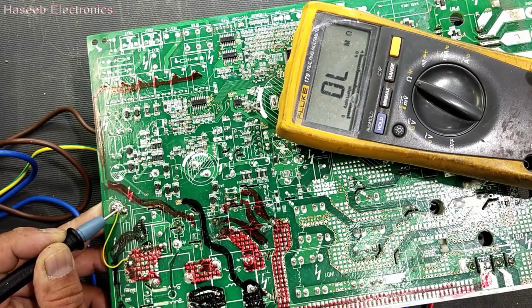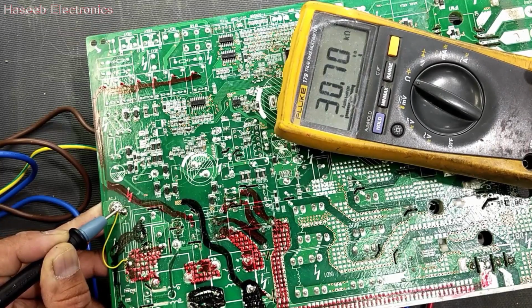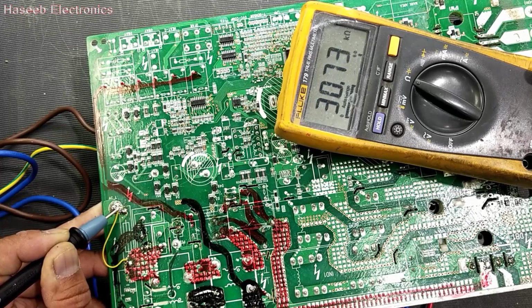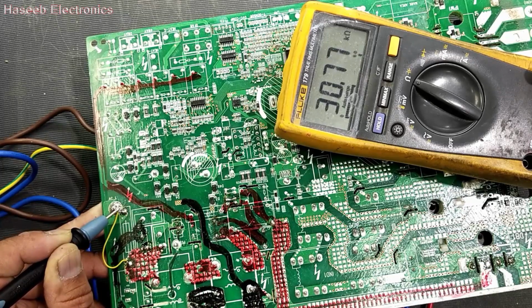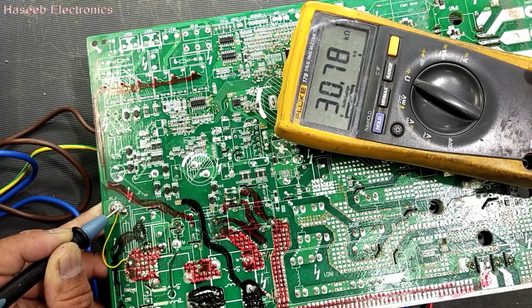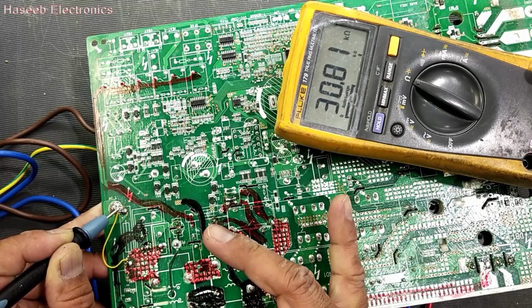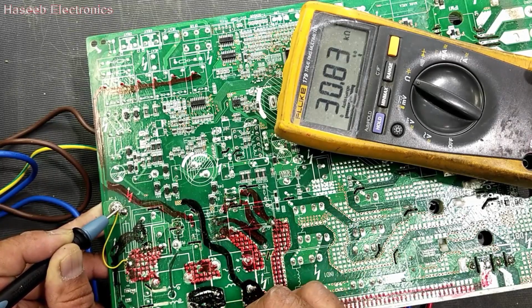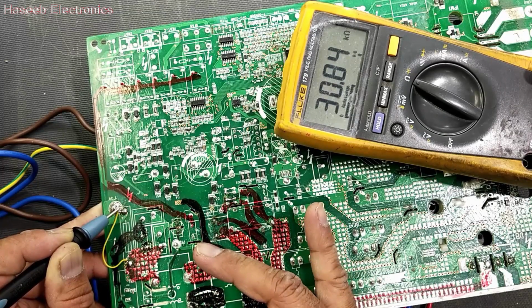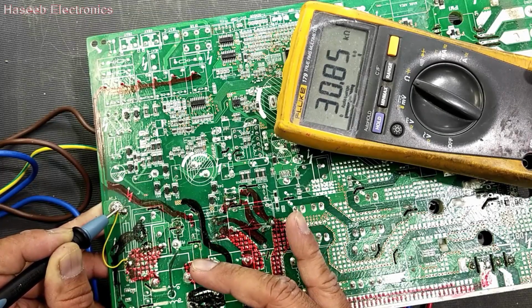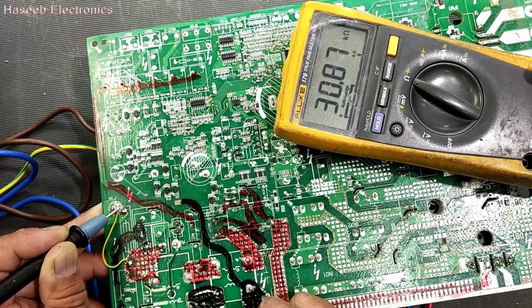Then check between the neutral line. We have 30.7K. This resistance is low and its value is increasing, so that means it is charging some capacitors. This is not a good indication - it must be in the hundreds of kilo ohms, 500, 600, 1 mega and above.